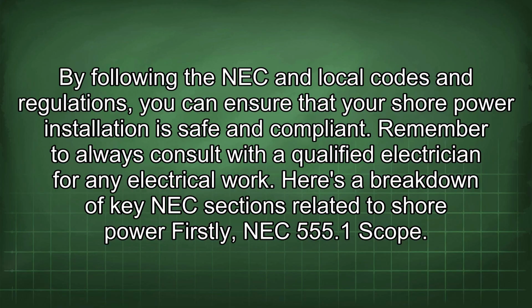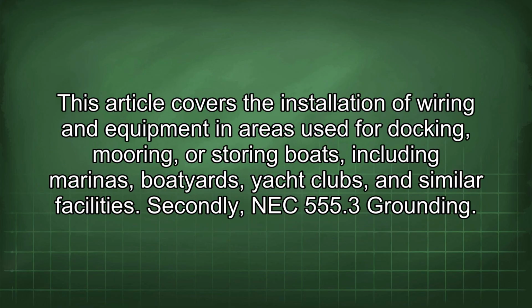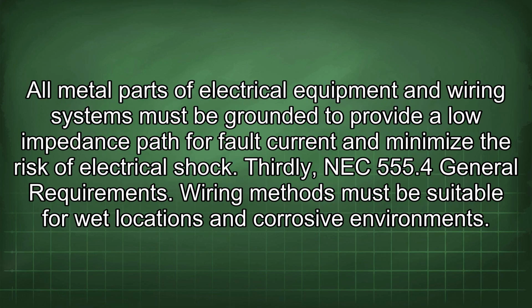Here's a breakdown of key NEC sections related to shore power. Firstly, NEC 555.1 Scope. This article covers the installation of wiring and equipment in areas used for docking, mooring, or storing boats, including marinas, boatyards, yacht clubs, and similar facilities. Secondly, NEC 555.3 Grounding. All metal parts of electrical equipment and wiring systems must be grounded to provide a low impedance path for fault current and minimize the risk of electrical shock.